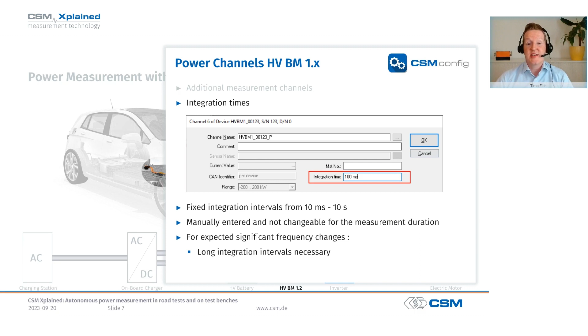Now it is important that you set the integration time for the power channels, and you can now freely select between 10 milliseconds and 10 seconds, and you simply enter the value in the corresponding field here, and this integration time is then fixed for the duration of the measurement. For signals with strong frequency changes, you should then enter longer integration intervals, because otherwise the power calculations can become inaccurate.